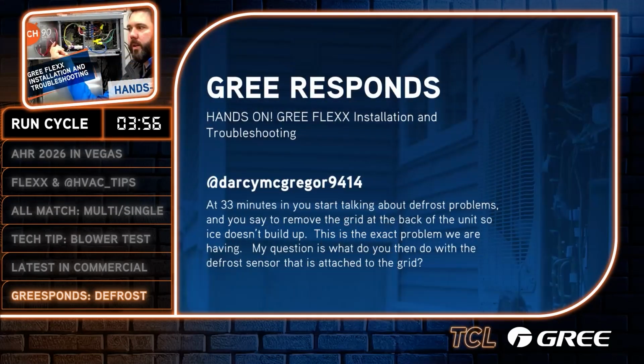I want to point out too, this isn't something you have to do every time. There's only been a handful of instances where we actually had ice build up from the environment itself and not from a defrost issue, like low charge, for example. It's really in cold locations when this happens. We've seen freezing fog off of rivers, like up in the Dakotas, and lake effect applications like that. It's like, okay, it needs all the help it can get.